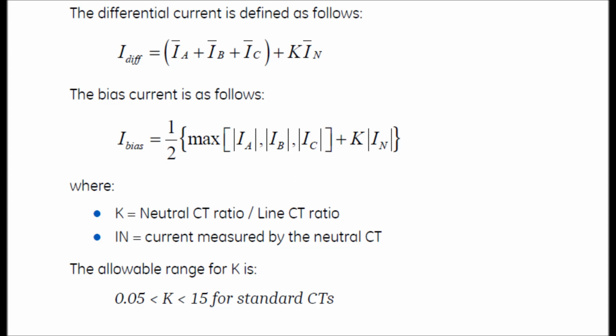This is nothing but a scalar value. Under through fault condition or under fault condition, among IA, IB, IC, whichever is maximum, this maximum value is taken plus K into IN for the bias current, where K is the factor given by the neutral CT ratio by the line CT or phase CT ratio.